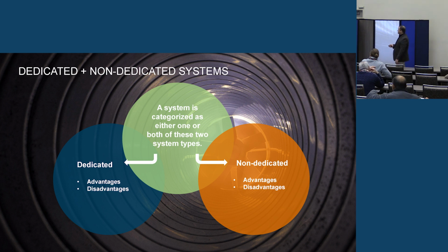Okay, so going back, this is kind of the summary: you really need to understand whether your system is dedicated or non-dedicated. The advantage of non-dedicated is that a lot of that system is getting exercised on a regular basis. The maintenance is going to naturally happen every time you have belt problems. You're already calling the mechanical contractor. The louvers are being exercised when the mechanical contractor comes out. There's probably somebody more familiar with it because they're working on it pretty regularly in a large building. Disadvantages: it's constantly being exercised and I constantly have mechanical contractors working on it. So when I need it, it might not be programmed right anymore. Again, that's why I like a life safety contractor involved on the smoke control component for any of the maintenance.